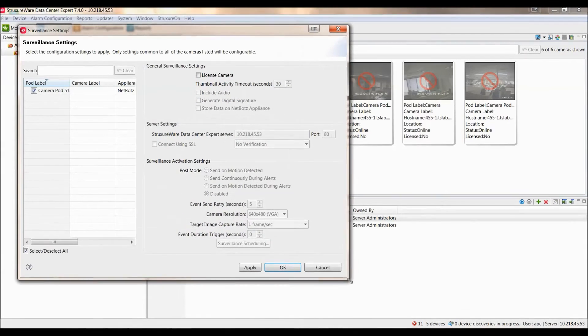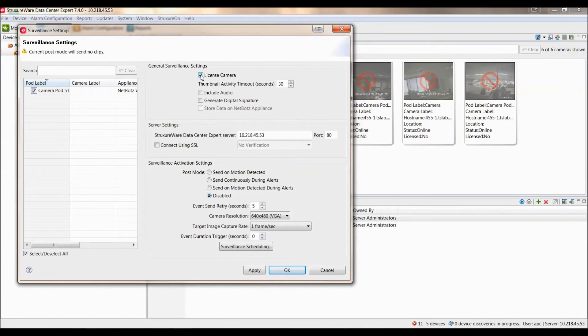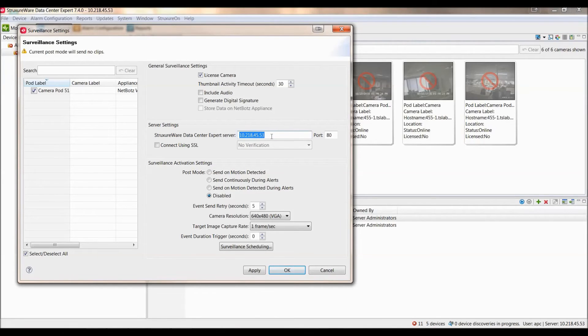Within Surveillance Settings, you are going to want to check the checkbox for License Camera, which enables the camera for surveillance within Data Center Expert and will use one of those surveillance licenses that we were just looking at. Under Server Settings, you are going to want to make sure to set the StruxureWare Data Center Expert Server IP address or hostname here.